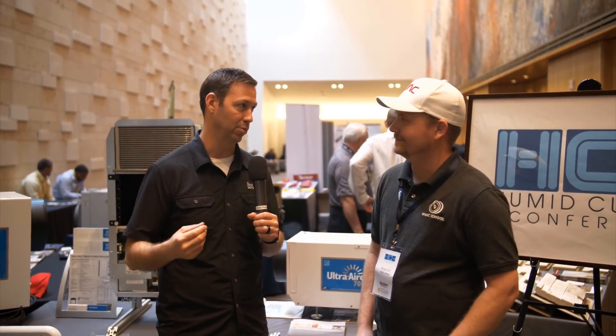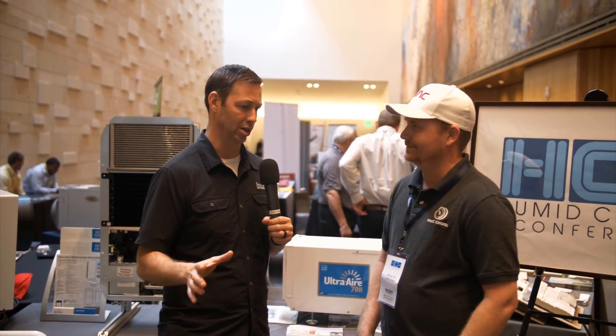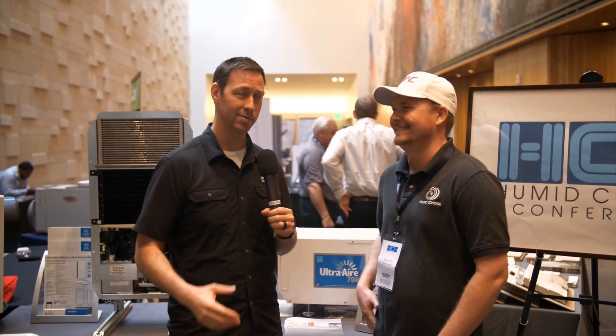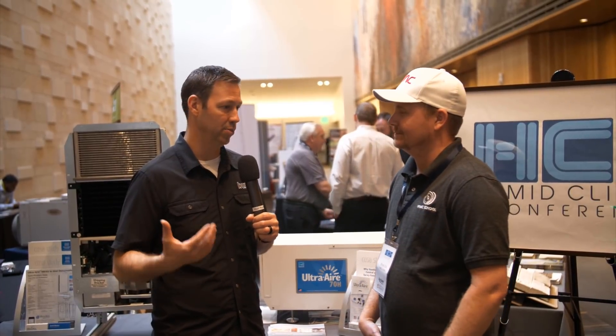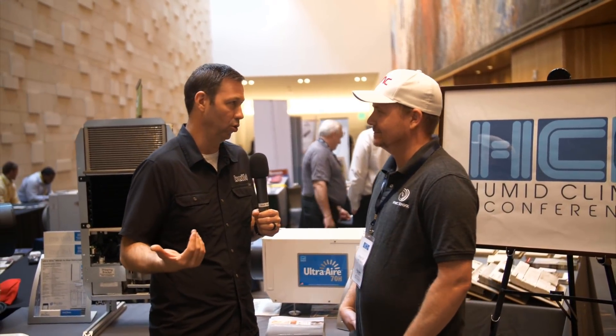My very first VRF house — the client was a super geek, he could have been an HVAC tech — and he said, 'Matt, we've been in here six months and I'm having a hard time keeping the humidity low. I don't want to be super cold; I want to keep the thermostat at 72. What do we do?' So we tweaked the system — it was a Mitsubishi — we put all the controls on it. And no disrespect to Mitsubishi, I still use their equipment all the time and I love them, but I don't think their bill of goods on 'this will totally control humidity' and their dry mode is really totally accurate.